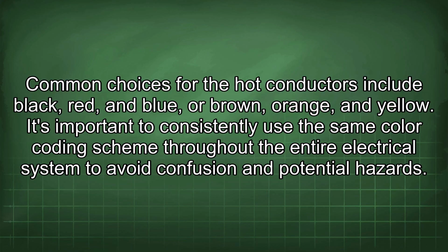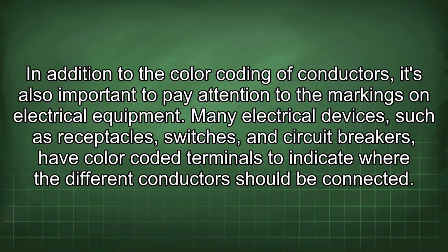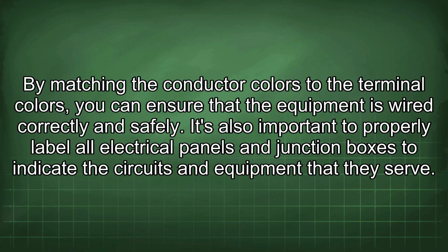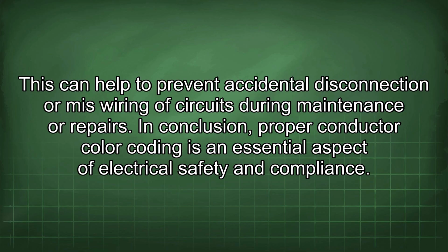It's important to consistently use the same color coding scheme throughout the entire electrical system to avoid confusion and potential hazards. In addition to the color coding of conductors, it's also important to pay attention to the markings on electrical equipment. Many electrical devices, such as receptacles, switches, and circuit breakers, have color-coded terminals to indicate where the different conductors should be connected. By matching the conductor colors to the terminal colors, you can ensure that the equipment is wired correctly and safely. It's also important to properly label all electrical panels and junction boxes to indicate the circuits and equipment that they serve. This can help to prevent accidental disconnection or miswiring of circuits during maintenance or repairs.